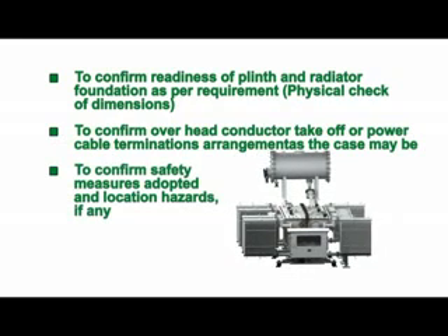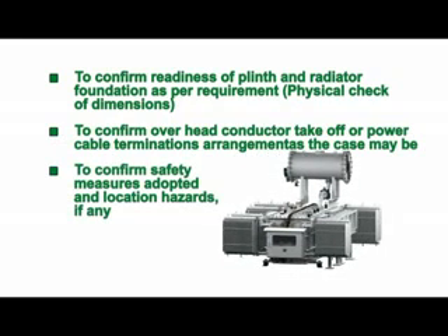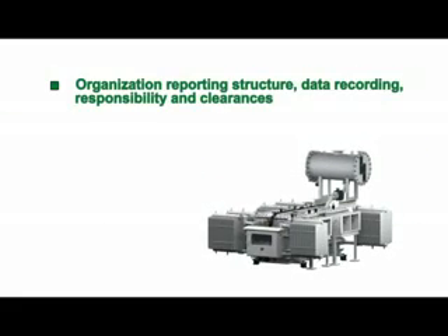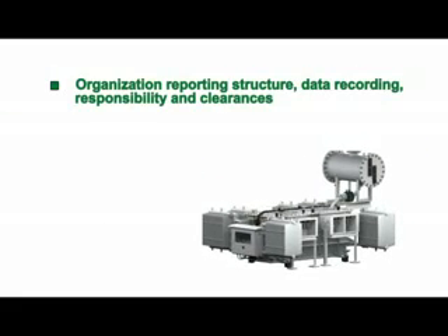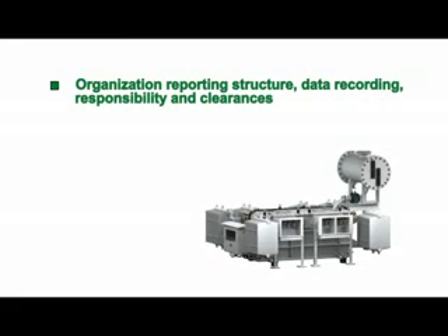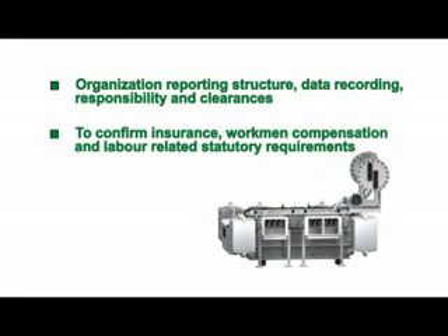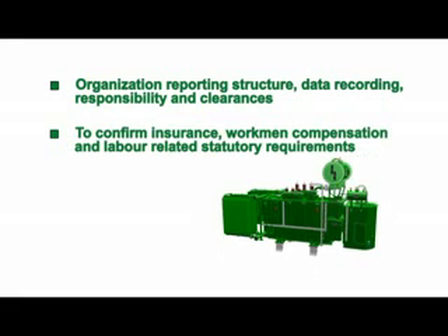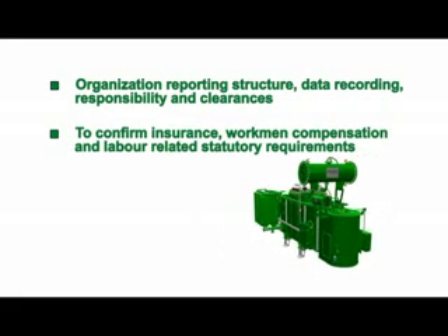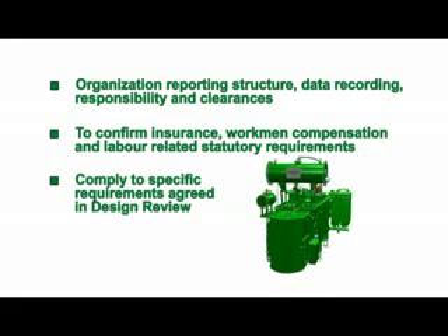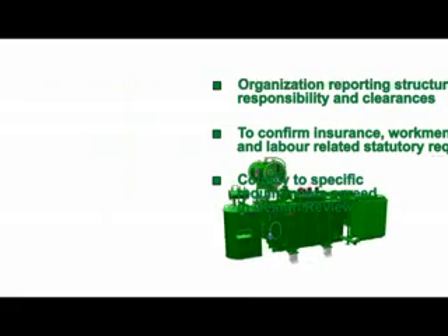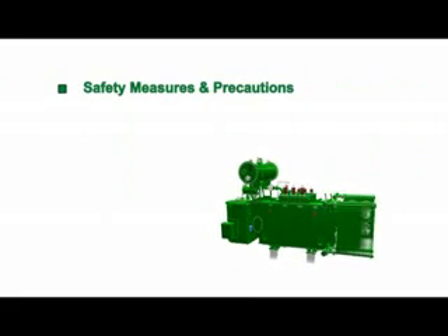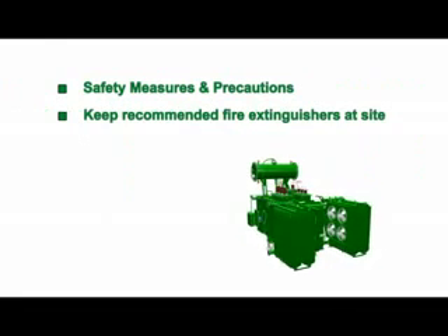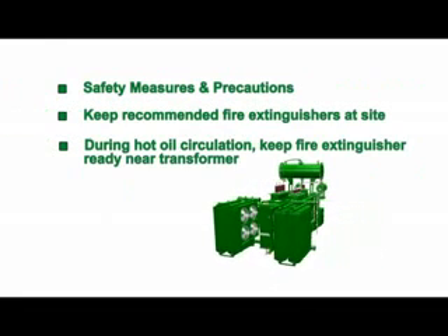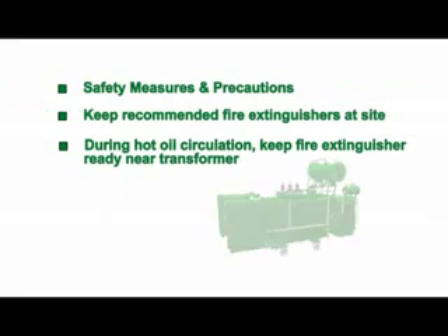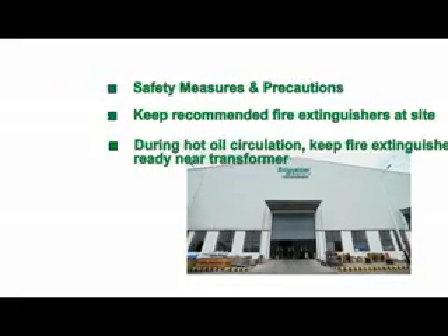To confirm safety measures adopted and location hazards, if any. Organization reporting structure, data recording, responsibility and clearances. To confirm insurance, workmen compensation and labor-related statutory requirements. Comply with specific requirements agreed in design review. Safety measures and precautions: keep recommended fire extinguishers at site. During hot oil circulation, keep a fire extinguisher ready near the transformer.